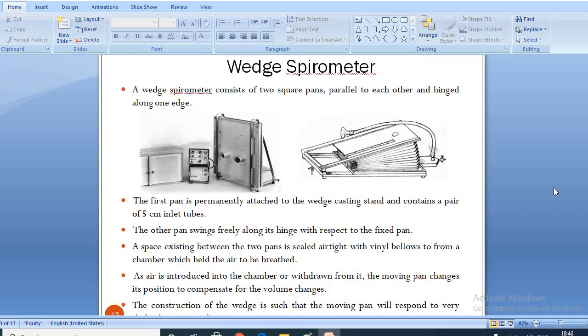The second type is a wedge spirometer. A wedge spirometer consists of two square pans parallel to each other and hinged along one edge. The first pan is permanently attached to the wedge casting stand and contains a pair of 5 cm inlet tubes. The other pan swings freely along its hinge with respect to the fixed pan. A space existing between the two pans is sealed airtight with vinyl bellows to form a chamber which holds the air to be breathed.